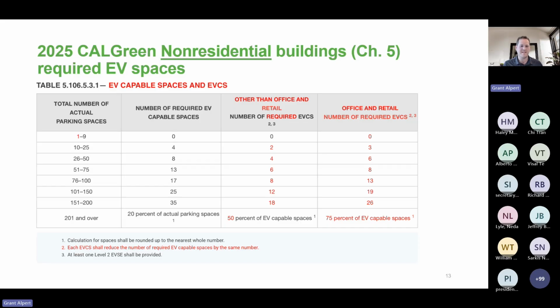If you don't want to deal with the EV capable spaces and finding conduit further along the line, so you're in office and retail and you see you need to have 3 chargers and 1 additional space, you can instead just install 4 EV charging stations. And in this sub bullet 2, each EV charging station shall reduce the number of required capable spaces by the same number. So that's just saying if you go up to 4 here, that's reducing this number by 1, and you can basically install EV charging stations to replace capable spaces and not be penalized for planning ahead with more charging stations than are required.